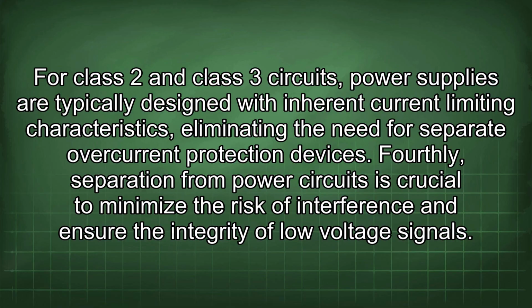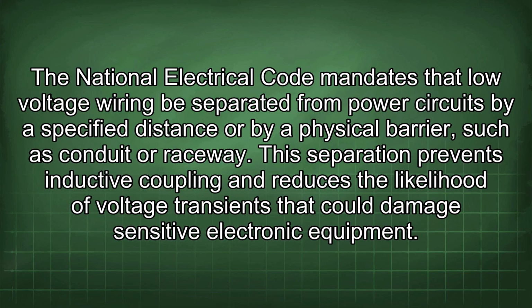Fourthly, separation from power circuits is crucial to minimize the risk of interference and ensure the integrity of low voltage signals. The National Electrical Code mandates that low voltage wiring be separated from power circuits by a specified distance or by a physical barrier such as conduit or raceway. This separation prevents inductive coupling and reduces the likelihood of voltage transients that could damage sensitive electronic equipment.